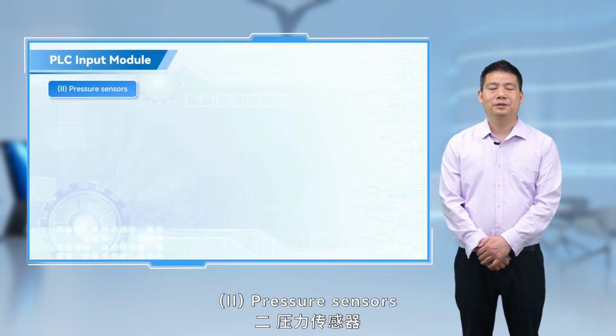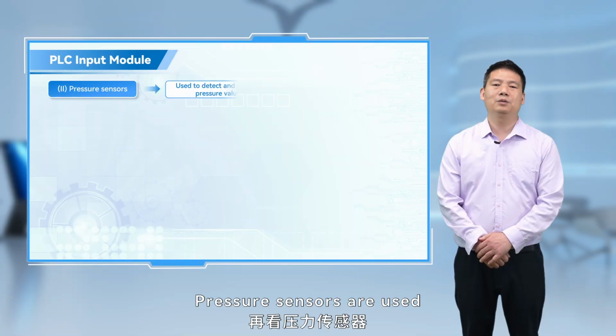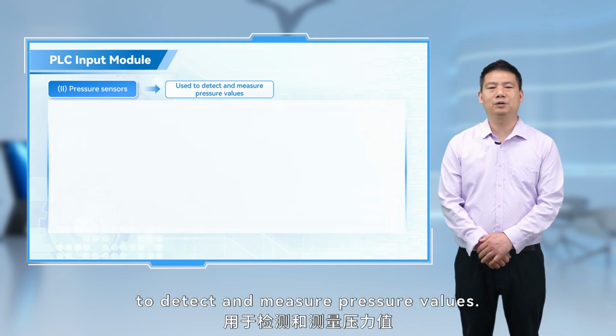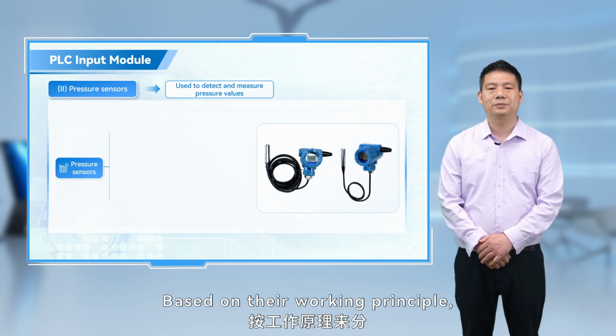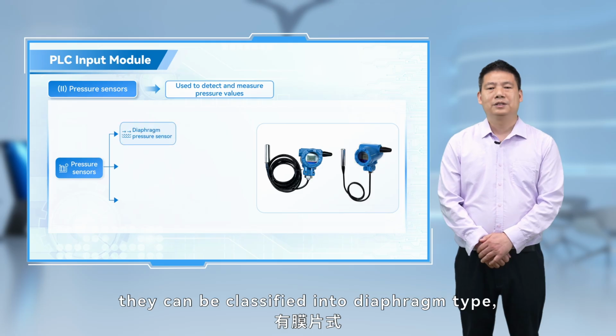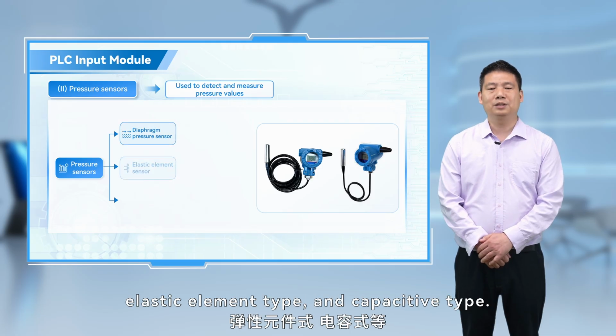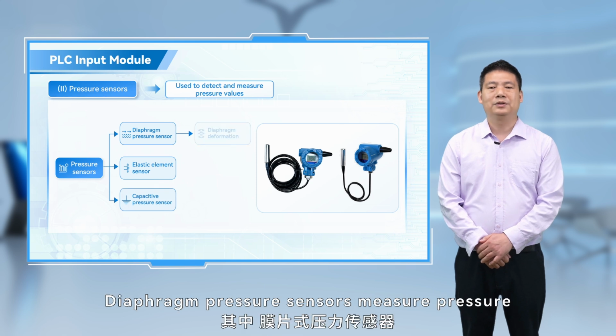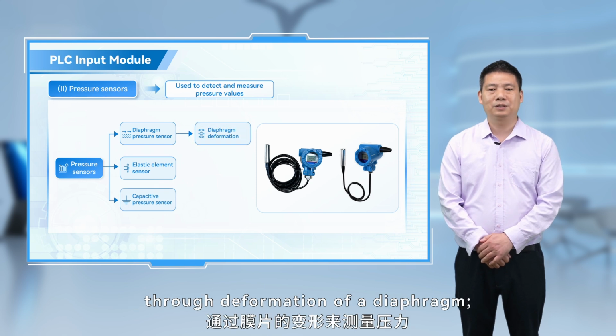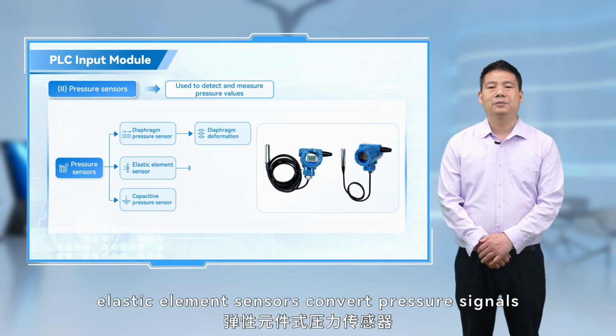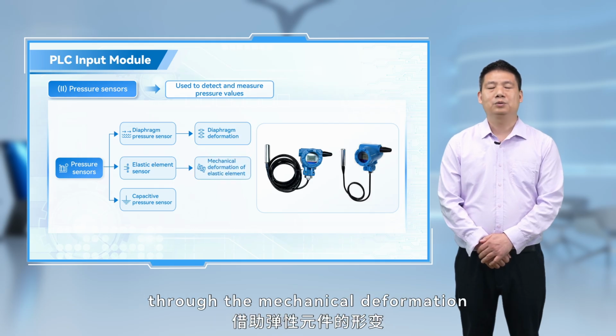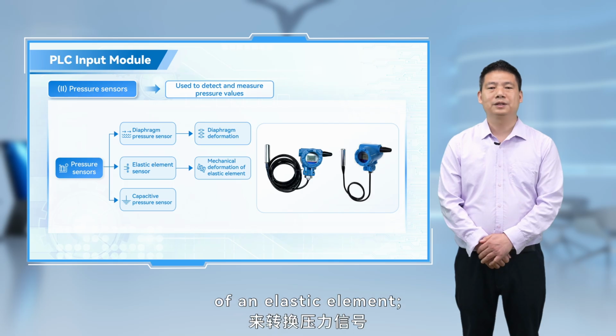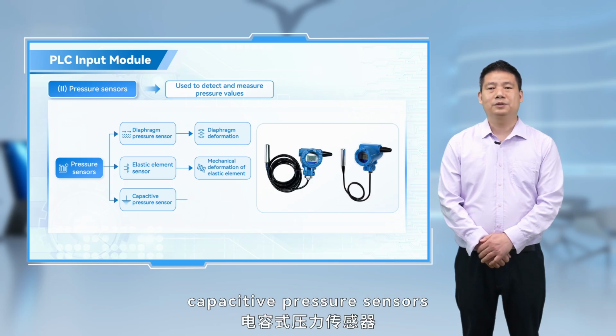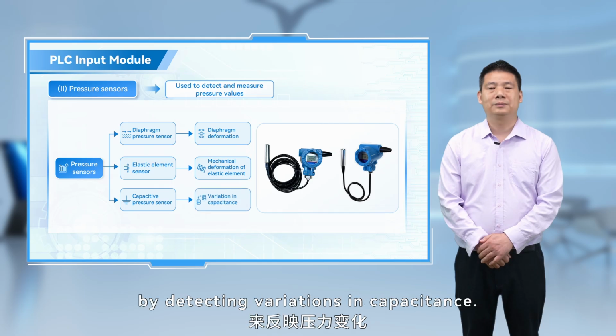2. Pressure sensors. Pressure sensors are used to detect and measure pressure values. Based on their working principle, they can be classified into diaphragm type, elastic element type, and capacitive type. Diaphragm pressure sensors measure pressure through deformation of a diaphragm. Elastic element sensors convert pressure signals through the mechanical deformation of an elastic element. Capacitive pressure sensors reflect pressure changes by detecting variations in capacitance.